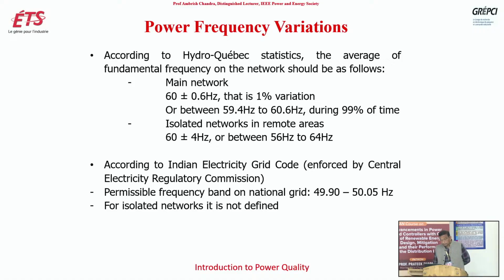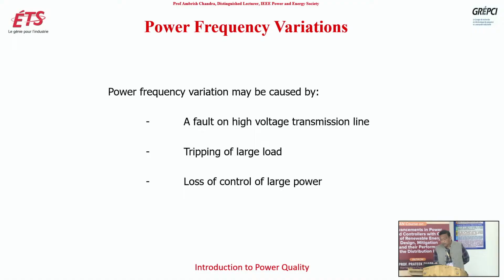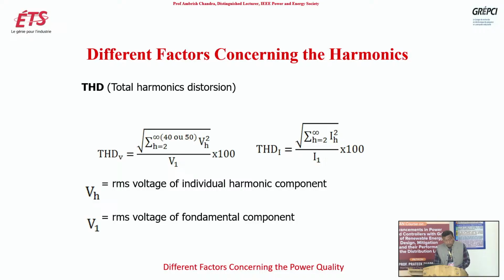But if they are there, they are working accordingly. Okay. Power frequency variation may be caused by a fault on a high voltage transmission line, tripping of a large load, or loss of control of a large power source. So these may be the reasons that power frequency variation may be there. Now, if you see the different factors concerning the harmonics, there are so many factors. So we need not go through all those factors. I will just discuss the basic one.